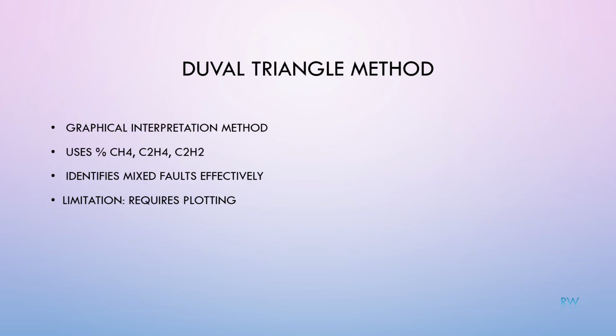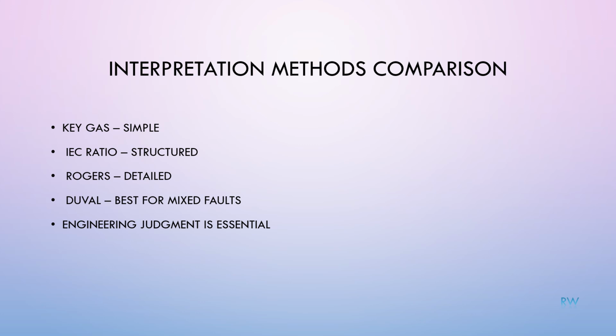The Duval triangle is a graphical method. It uses the percentage of methane, ethylene, and acetylene to plot a point inside a triangle. Based on the location inside the triangle, the fault type is identified. This method is very effective for mixed faults and is widely accepted. No single method is perfect. The key gas method is simple but basic. The IEC and Rogers ratio methods are structured but require calculations. The Duval triangle provides better accuracy for mixed faults but requires plotting. Proper engineering judgment is always required.